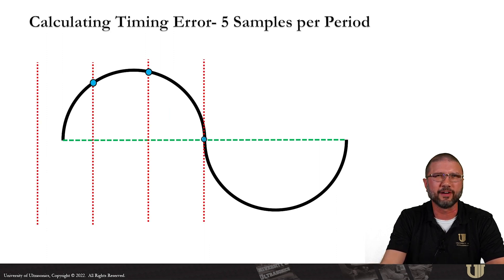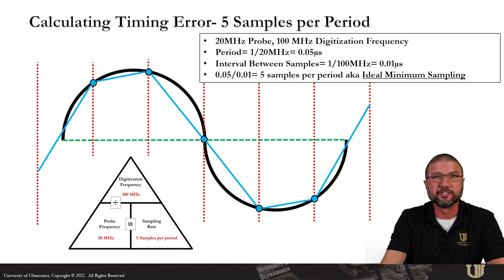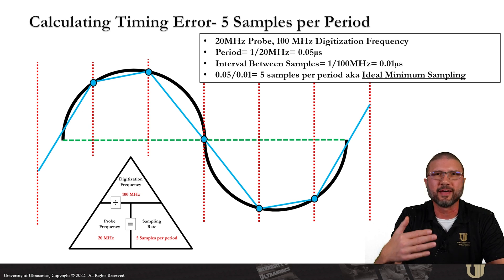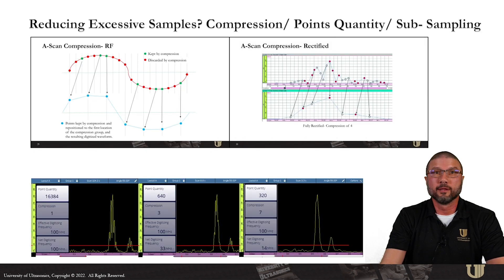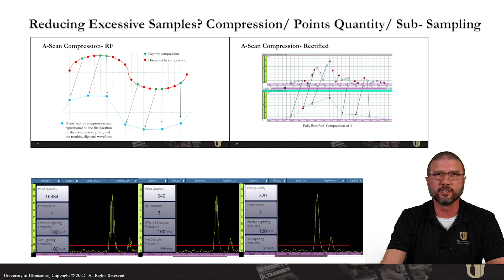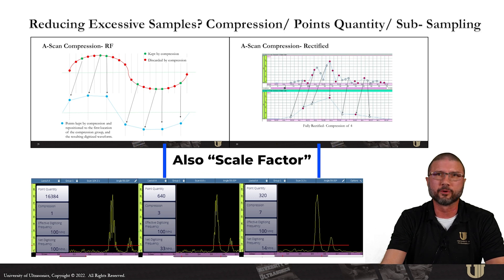Why would a manufacturer set 100 megahertz or even 125 megahertz as a default or max digitization frequency? Simply to make sure we can achieve ideal sample rates with any of the probe frequencies compatible with the instrument — the higher the probe frequency, the higher the digitization rate needs to be. This leads us to our last scenario: a 20 megahertz probe with a 100 megahertz digitization frequency, giving us five samples per period and achieving ideal minimum sampling. Some instruments allow you to directly adjust the digitization frequency; others let you adjust what we call a net digitizing frequency via compression — also known as points quantity or sub-sampling — which I'll cover in a later video.